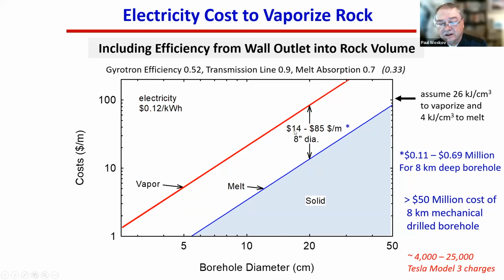So the cost to melt or vaporize falls in the range of $14 to $85 per meter of penetration. This is assuming a 12-cent per kilowatt hour cost. This is not the cost we're paid for with all the transmission costs and others added to it. So this is for 26 kilojoules per cubic centimeter to vaporize and 4 kilojoules per cubic centimeter to melt, which is the mean of the number range that I gave in the previous viewgraph.